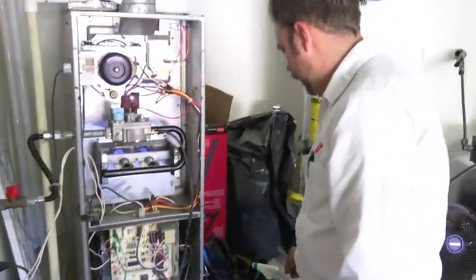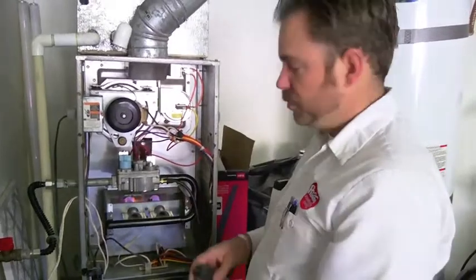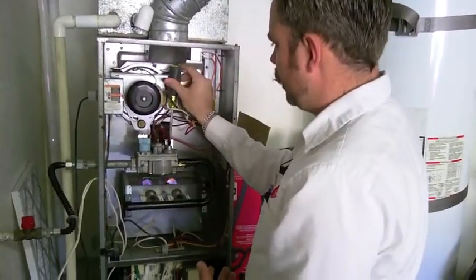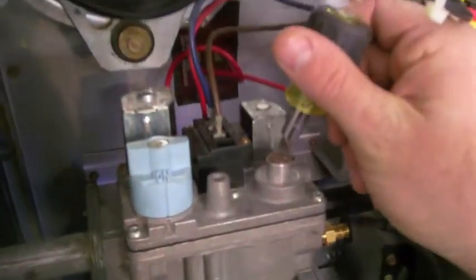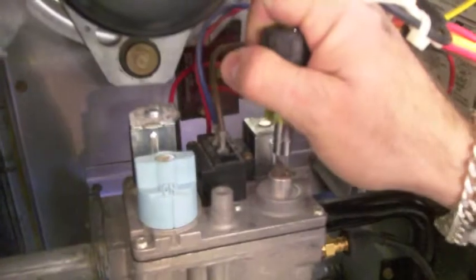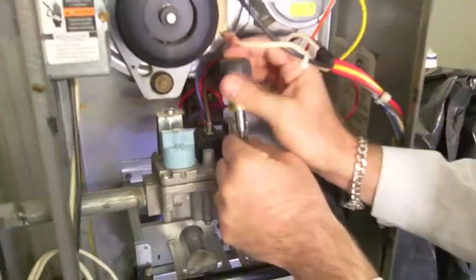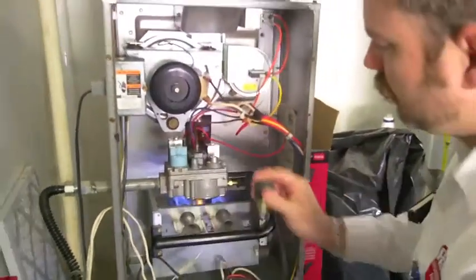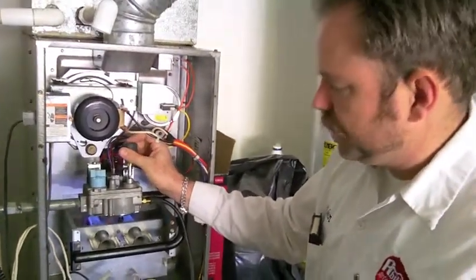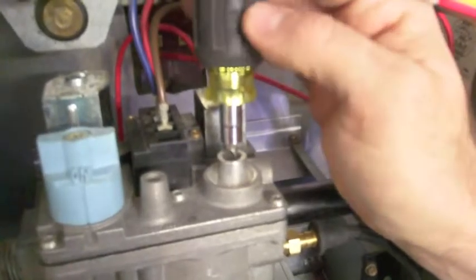Another point on this is that if you needed to adjust the gas pressure, you can do that by this little screw up here on the top. You adjust this little screw on the inside here. If you turn it counterclockwise, it's going to decrease the pressure. If you turn it clockwise, it's going to increase the pressure.